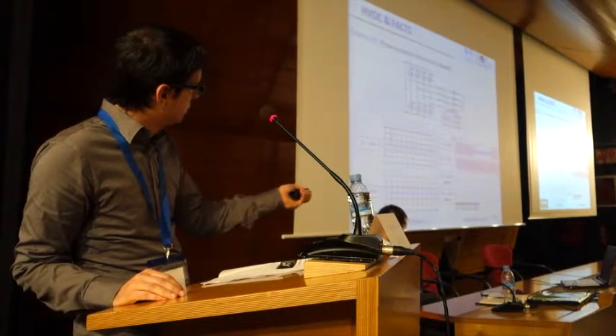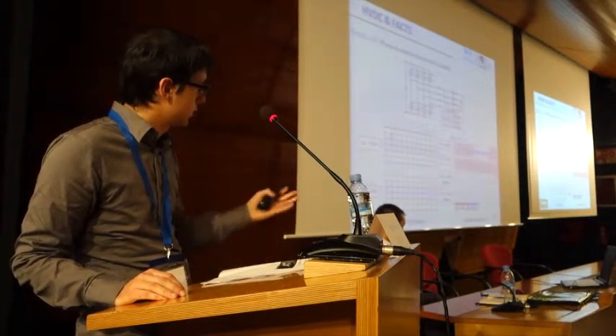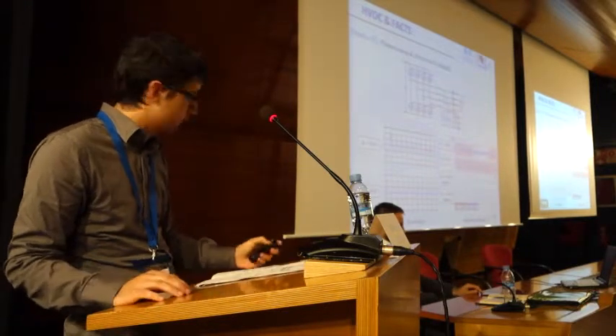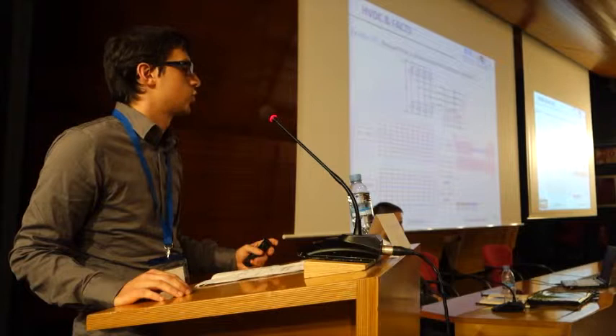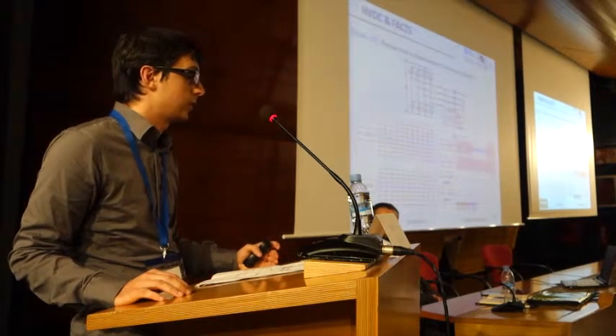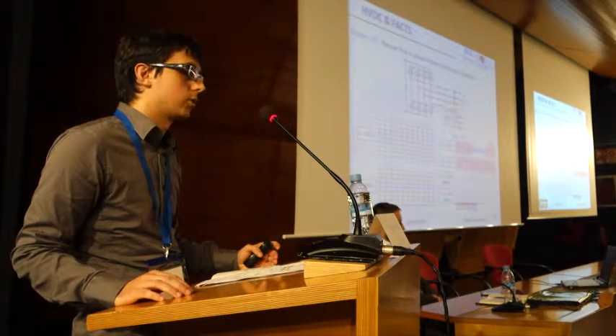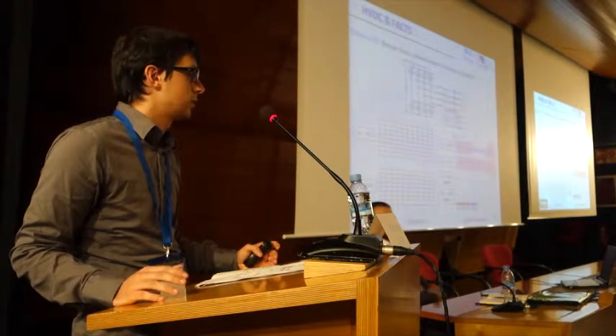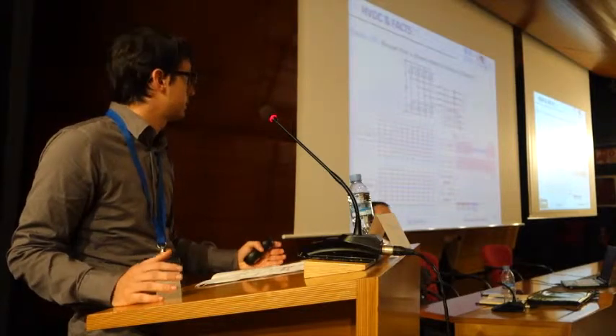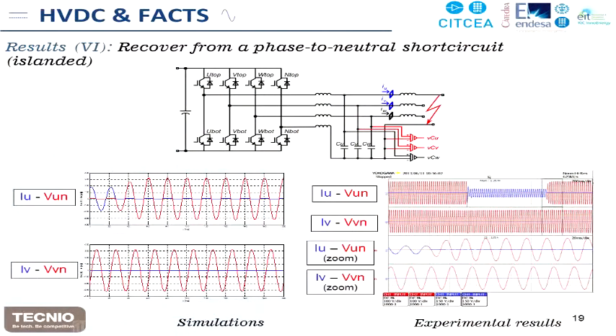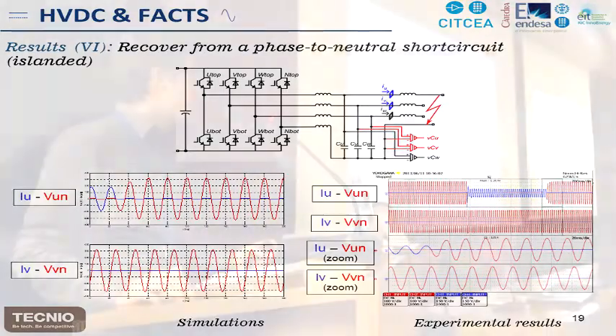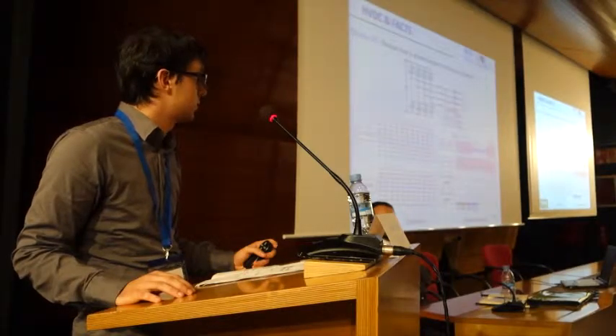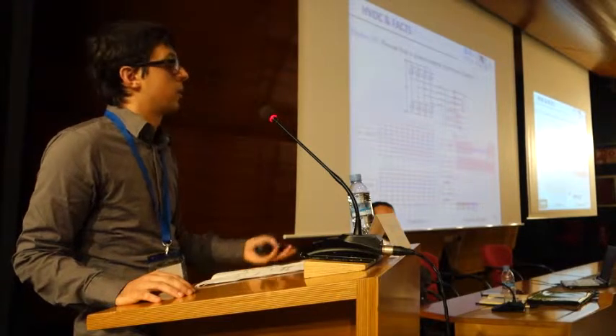Here we also have the experimental and the simulation results, which support each other. Finally, it's also important not only to support the fault, but also the moment when the fault is recovered. Considering that we can have some load connected to the AC side, it's important that this load doesn't see any overvoltage, in order to maintain the integrity of that load. In this case, the system shows that it is able to progressively adapt the voltage from 0 to the nominal value without any overvoltage. This implies that this system in island operation mode is able to support short circuits and also the fault recovery without any problem.